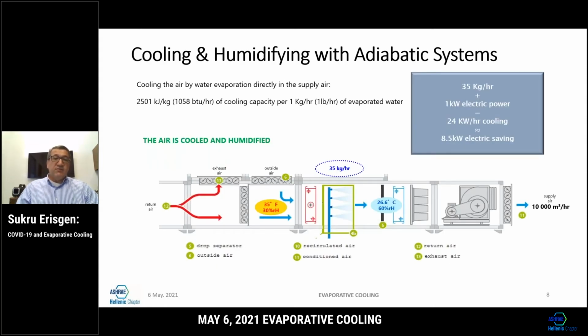So when we look at the comfort cooling side of it, you can see a typical application here. You may have seen this. You can have a return air, you can exhaust it, a simple air handling unit. Using 35 kilograms an hour of water and 1 kilowatt of electricity, and these are just hypothetical numbers, we can achieve approximately 24 kilowatts of cooling. I converted these from BTUs, so there may be some rounding errors, but this is approximately 8.5 kilowatts of electric savings. So using 1 kilowatt of electricity and 35 kilograms an hour of water, we can achieve significant electric savings in an example of 10,000 cubic meters an hour air supply.